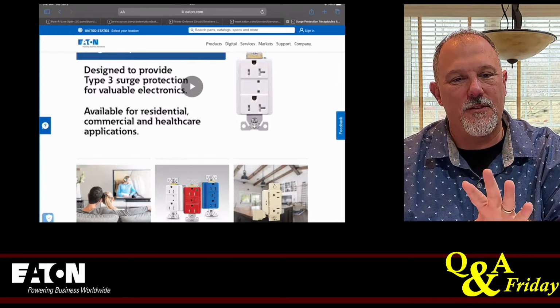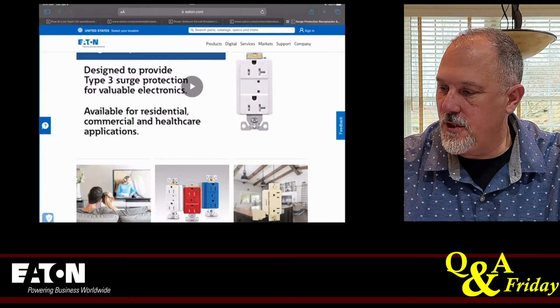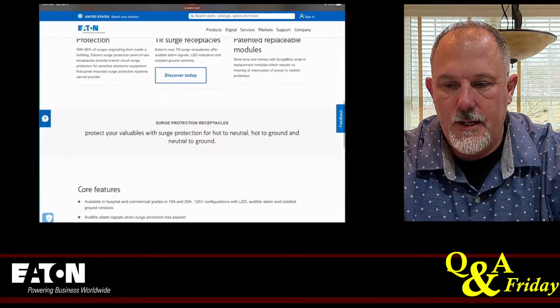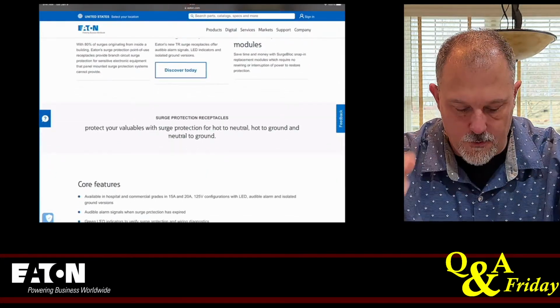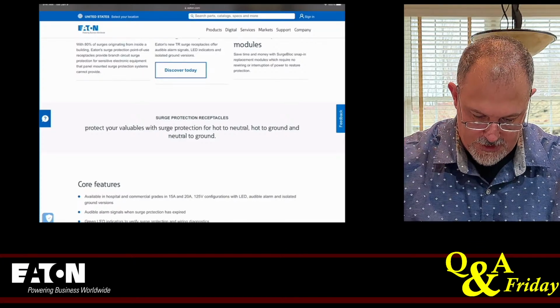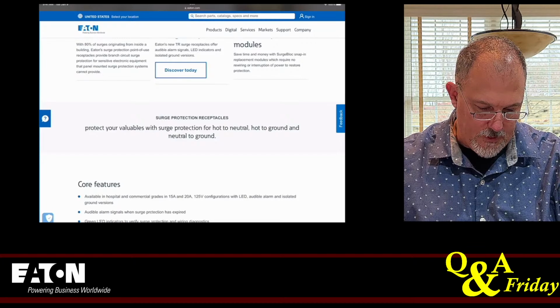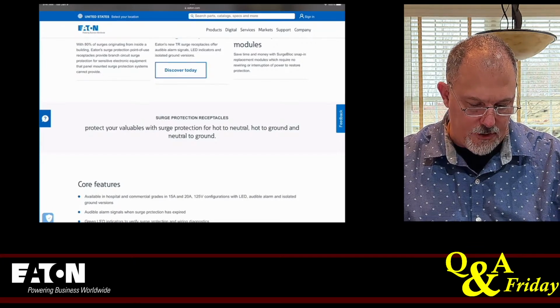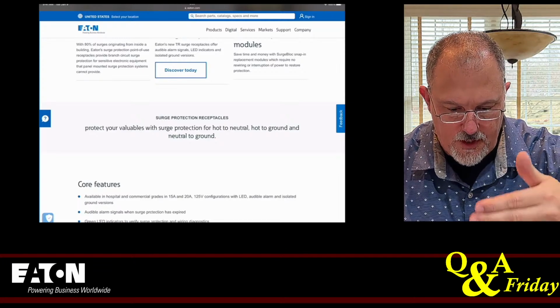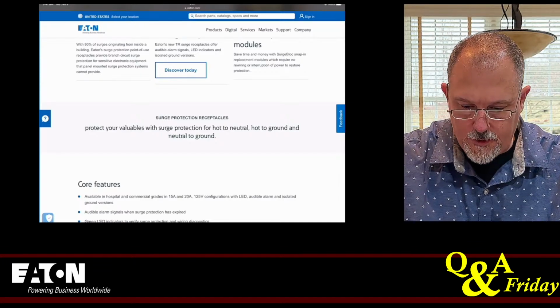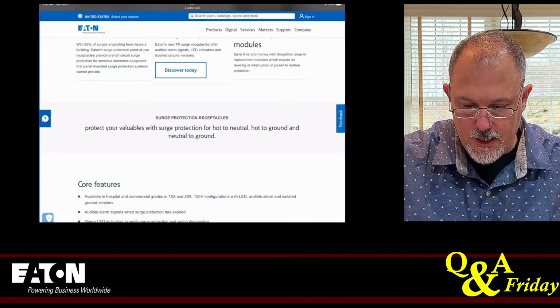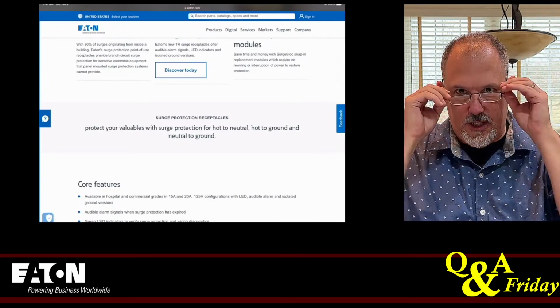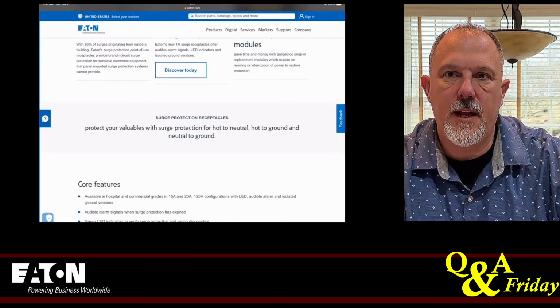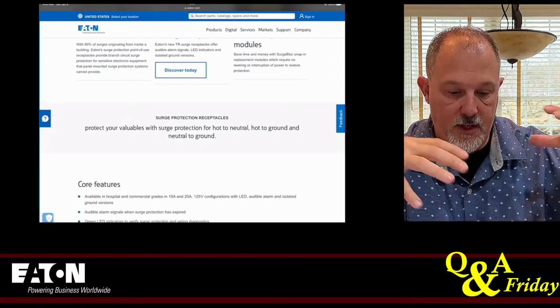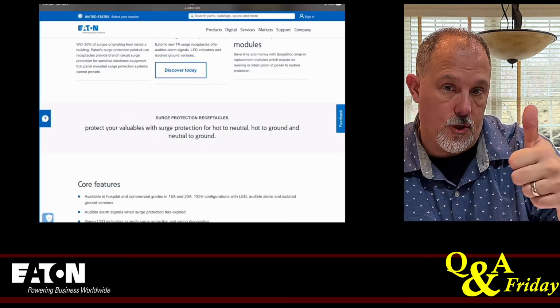So both of those standards are covered, and you don't have to worry about how many. You just follow the rules in 210.21, Table 210.21(B)(3). So 210.21(B) is your single receptacle. 210.21(B)(3) is your receptacle ratings where connected to a branch circuit supplying two or more receptacles. You have the table 210.21(B)(3) that tells you how many you can put on it. Don't worry about if you have a 15 amp receptacle and you have it on a 20 amp branch circuit. If you're following the rules in the code for receptacles, you're good to go. All right. And that's all I have to say about that.